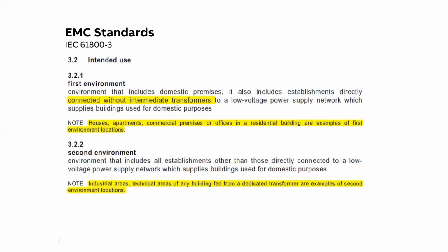This IEC has divided basically two different kinds of environment: first environment and second environment. So wherever we are applying this code, or wherever these devices are, first we have to check whether it is in the first environment or second environment. First environment is basically any network or any premises which is directly connected to a public low voltage network or directly connected to a public transformer. So most of our commercial and residential buildings fall under the first environment, and second environment is any premises which is not connected directly to a public low voltage network, but it has an intermediate transformer. So such an installation falls under second environment.